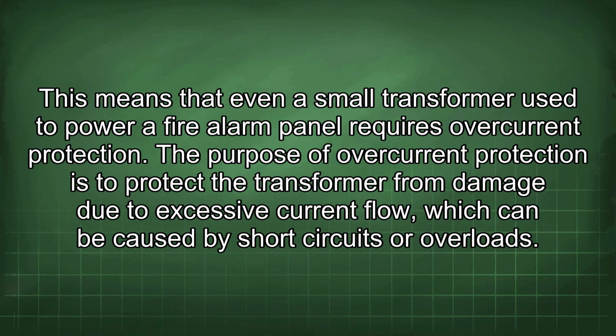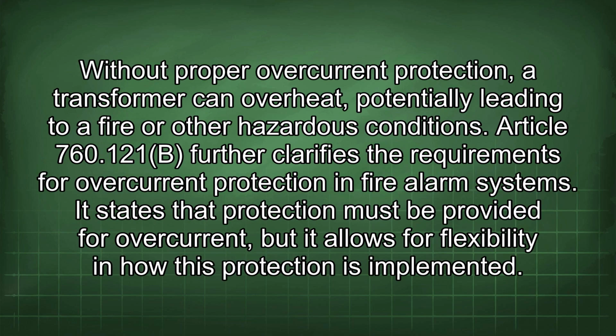The purpose of overcurrent protection is to protect the transformer from damage due to excessive current flow, which can be caused by short circuits or overloads. Without proper overcurrent protection, a transformer can overheat, potentially leading to a fire or other hazardous conditions. Article 760.121(B) further clarifies the requirements for overcurrent protection in fire alarm systems.